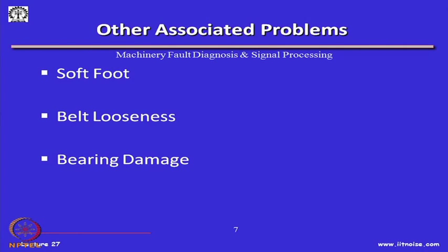Associated problems include soft foot, belt looseness, and bearing damage — if loose components go undetected, they impose excessive forces on bearings, eventually damaging them. One defect leads to another, which is why early detection in condition monitoring is critical. If the initial defect goes unnoticed, it can develop into a more severe problem that is difficult to diagnose.